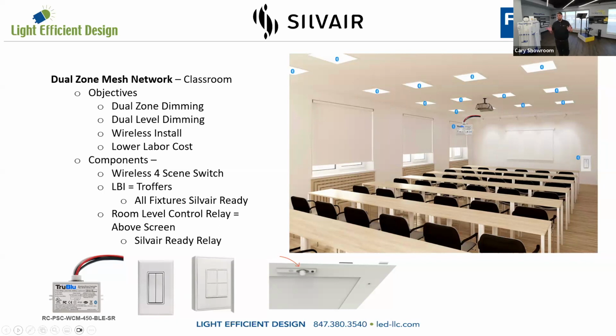In this situation, you're really just shutting the track lights on and off unless they have 0 to 10 volt dimming, which isn't that common, but you can at least shut them off during a presentation so the board looks nice and bright, and dim the fixtures down as well in the programming with different sets.